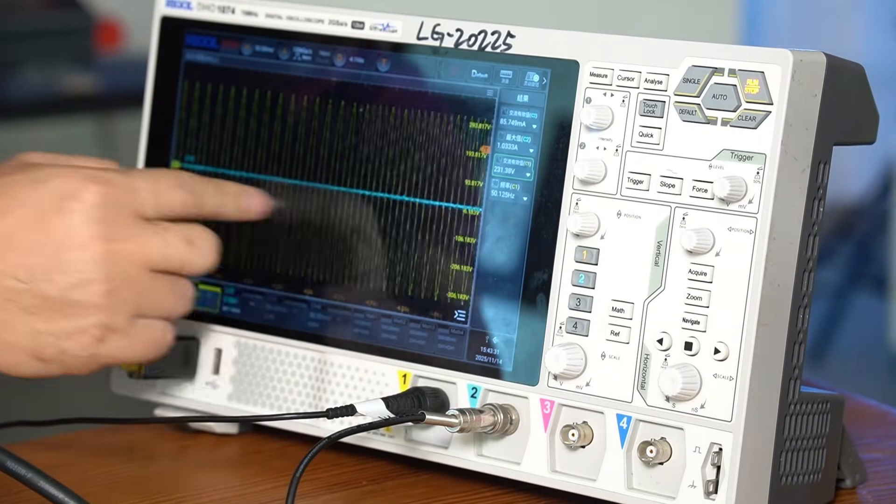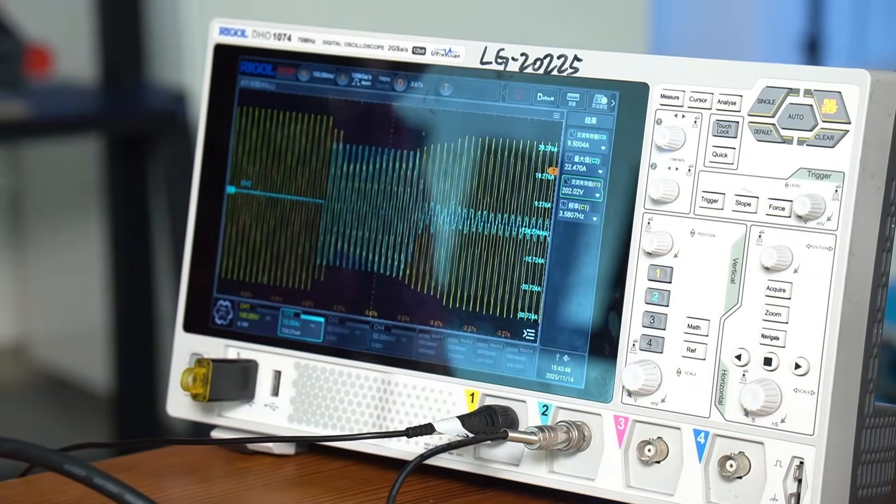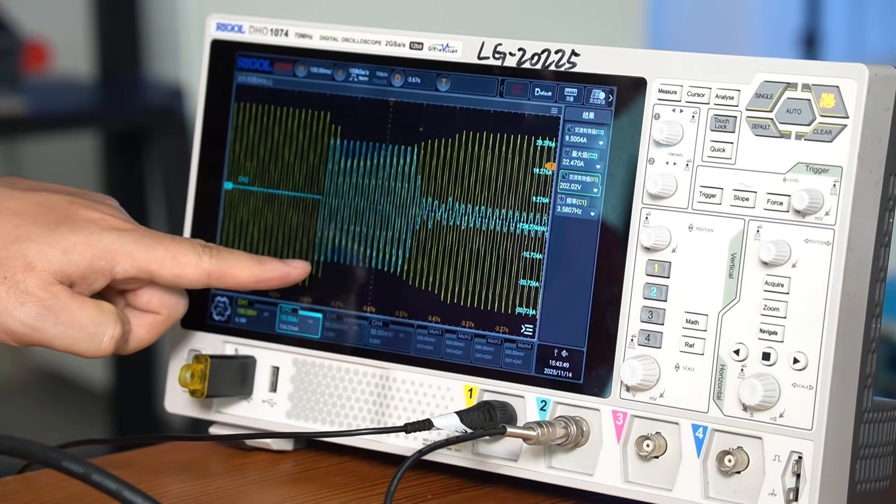By zooming in and out on the waveform, we can clearly see that the maximum peak current appears in this area and is a relatively stable waveform section. It's the current after the compressor enters normal operation.